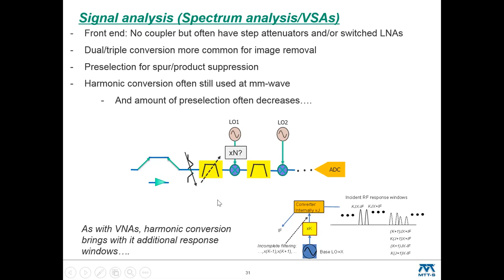Going towards millimeter wave, there tends to be a bit less of a difference from the network side. The pre-selection typically gets a little bit weaker since the losses through those kind of structures at 70, 80, 100 gigahertz can be substantial. They still exist, but they can be larger. You may have the harmonic conversion we talked about before, so the same kind of issues might creep in with other harmonic products. And certainly the older school millimeter wave harmonic mixers one might have used, there's no pre-selection at all, and there's a whole forest of these of significant amplitude.